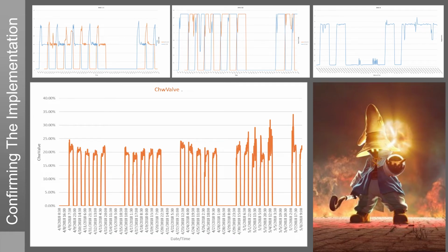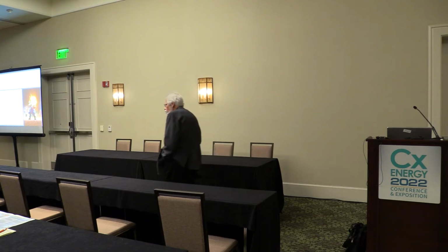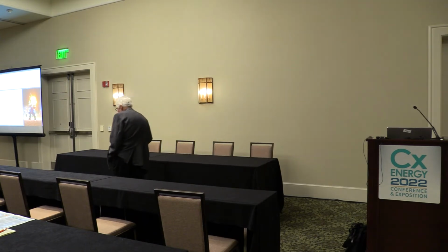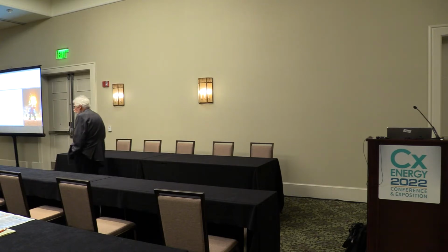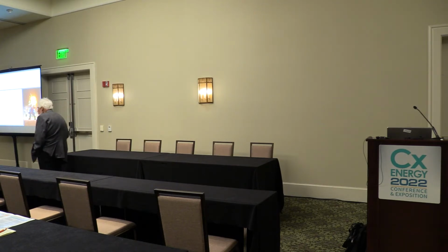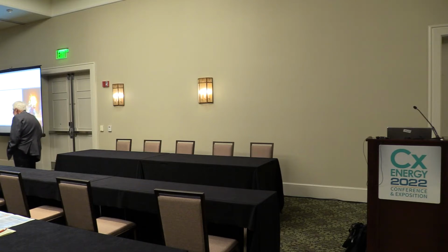These are actual trends, and we found some interesting things. If anybody here knows what static pressure reset is — well, if you ever wonder if it works, it works. We found air handlers that would normally sit at 1.5 inches all the time; we saw some go down to 0.6 and sit there most of the time. Think about that — I'm not going to go through the fan affinity laws, but if you cut by 20%, the energy savings is phenomenal.